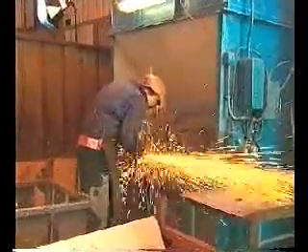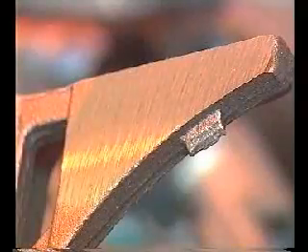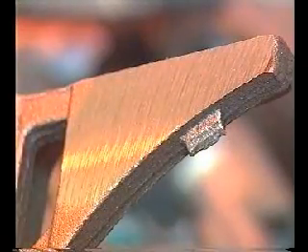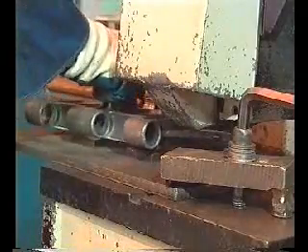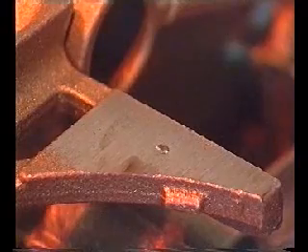The test area is quickly and simply prepared by hand in a similar or simpler method than they would be for measurement using a manual microscope. This standard of surface finish is adequate. The casting is transferred to the Brunscan, which makes and measures the Brinell indentation. Once they have been tested, castings which have been rejected are put into a bin, and those within the specified hardness range are stacked on a stillage.